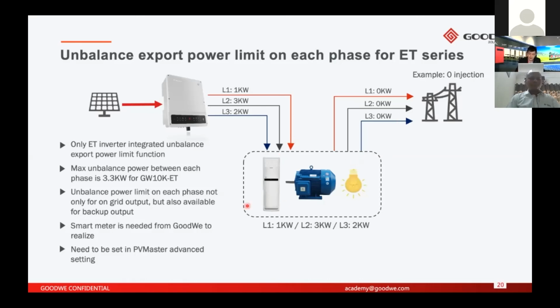You can find this case: phase 1 is 1 kilowatt, phase 2 is 3 kilowatt, phase 3 is 2 kilowatt. If the inverter doesn't support the unbalanced export power limit, the inverter will output 1 kilowatt on each phase: phase 1 is 1 kilowatt, phase 2 is 1 kilowatt, phase 3 is also 1 kilowatt. In this case, the customer will lose a lot of generation on the PV side. If the inverter can support unbalanced export power limit, that means the inverter can output the same power as the load consumption on each phase.